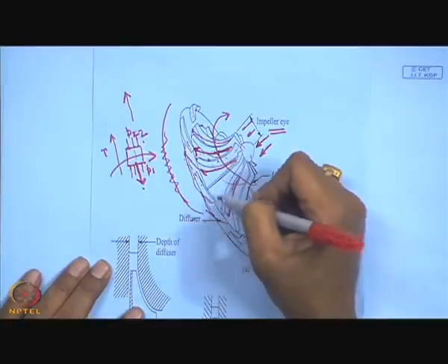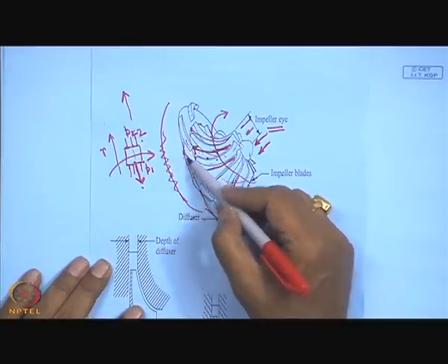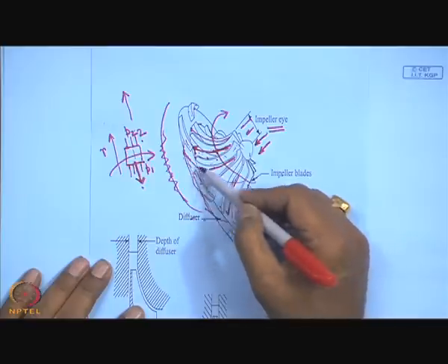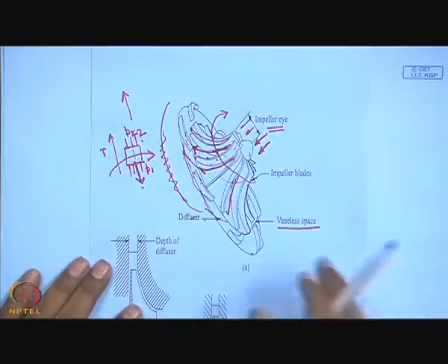In a pump, you have seen that a similar thing was made by a volute casing, where the fluid is decelerated to get high pressure of the water at the expense of its high velocity at the outlet of the impeller. But there we had a single volute casing without a number of passages created by this type of vane. But here the vanes are there to create a number of passages to divide the flow into small passages. I will come to that afterwards.